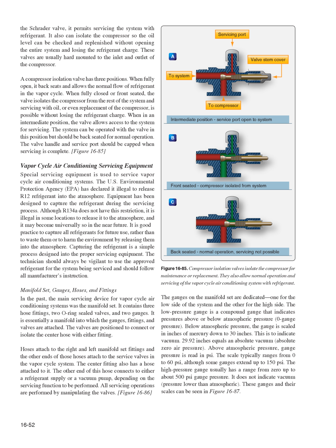In the past, the main servicing device for vapor cycle air conditioning systems was the manifold set. It contains 3 hose fittings, 2 O-ring sealed valves, and 2 gauges. It is essentially a manifold into which the gauges, fittings, and valves are attached. The valves are positioned to connect or isolate the center hose with either fitting. Hoses are attached to the right and left manifold set fittings, and the other ends of those hoses are attached to the service valves in the vapor cycle system. The center fitting also has a hose attached to it. The other end of this hose connects to either a refrigerant supply or a vacuum pump, depending on the servicing function to be performed. All servicing operations are performed by manipulating the valves.